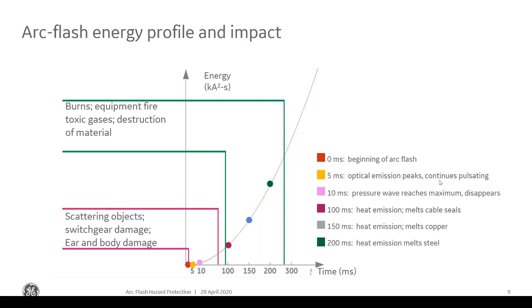Then at about 10 milliseconds, the pressure wave reaches its maximum, and then it starts to disappear. The heat emission at about 100 milliseconds starts to develop heat, which can melt cables, seals, and insulation. At about 150 to 200 milliseconds, the heat starts to melt metals such as copper and steel, which can release toxic vapors.